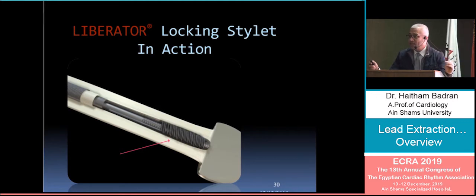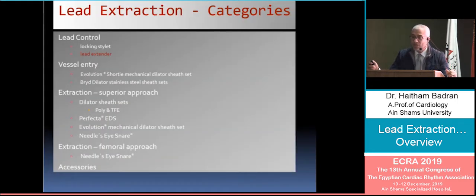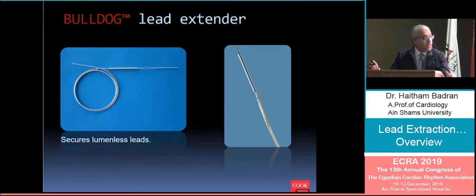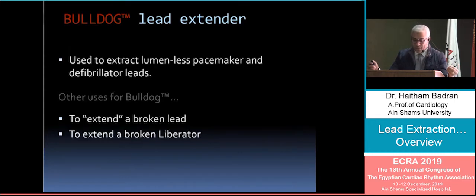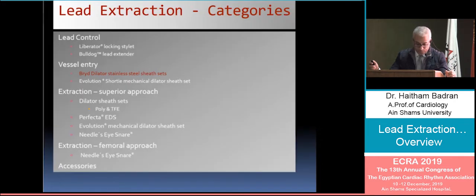So with the locking stylet, it is very important to be as far as possible inside the lead, and to make sure that it is stable inside the lead. It will not come out when you pull. So the locking stylet is the first step. But some leads are lumenless leads, and we don't have the possibility to enter a locking stylet inside. So they invented something called the lead extender, or the BULLDOG lead extender. It's similar to the locking stylet and can be used in order to extract lumenless pacemaker leads, and to extend a broken lead or broken liberator or locking stylet as well.